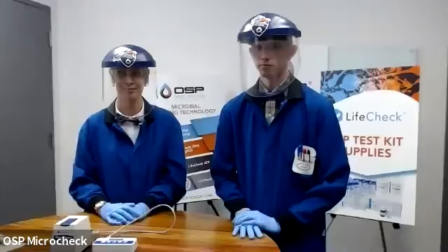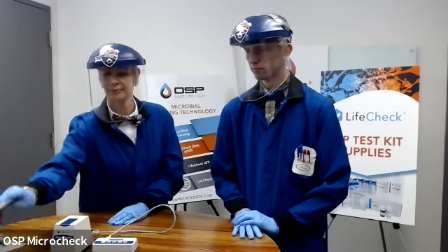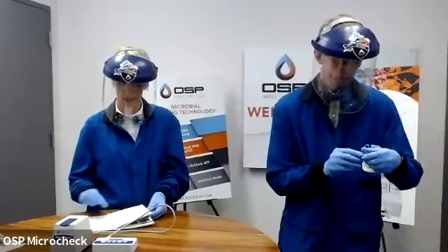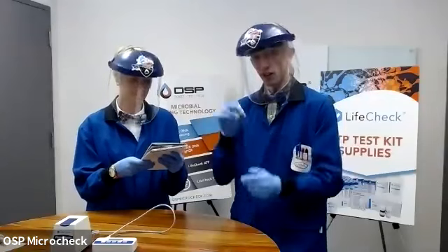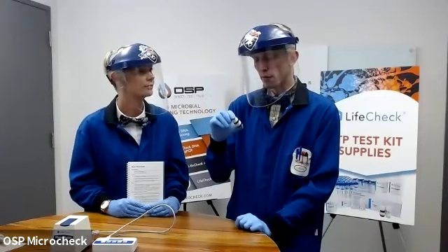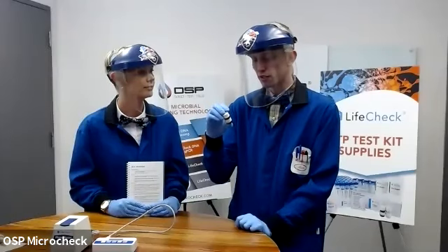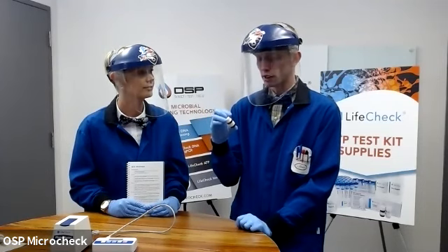All right, so the next question we have is, what is the shelf life for reagents, assuming all are kept in a controlled temperature environment? It does depend on each individual reagent, and it will say on the bottles. For example, I'm looking at the reagent that is the enzyme here. So this is stable for 3 months after hydration if you store it in a refrigerator, so 4 degrees centigrade. Stable for 6 months after hydration if you freeze it to -20. And otherwise, it has an overall expiry date based on the lot number.